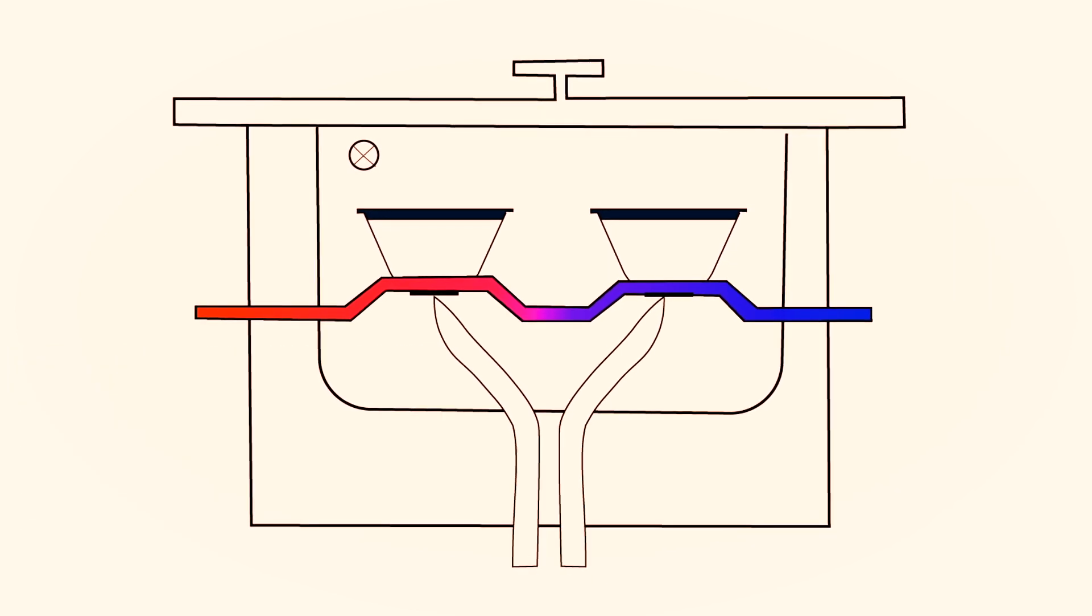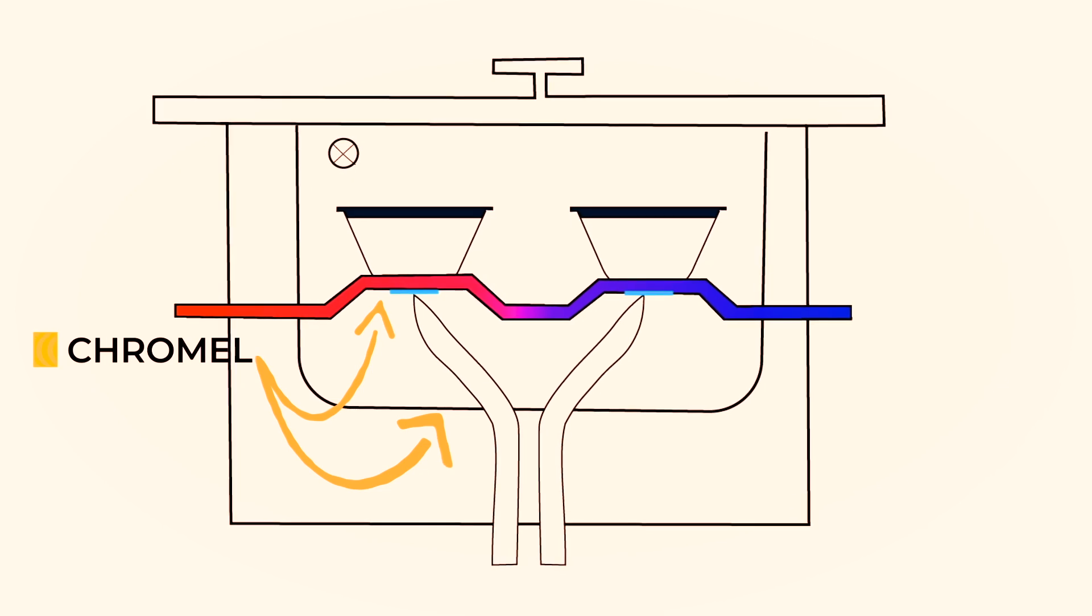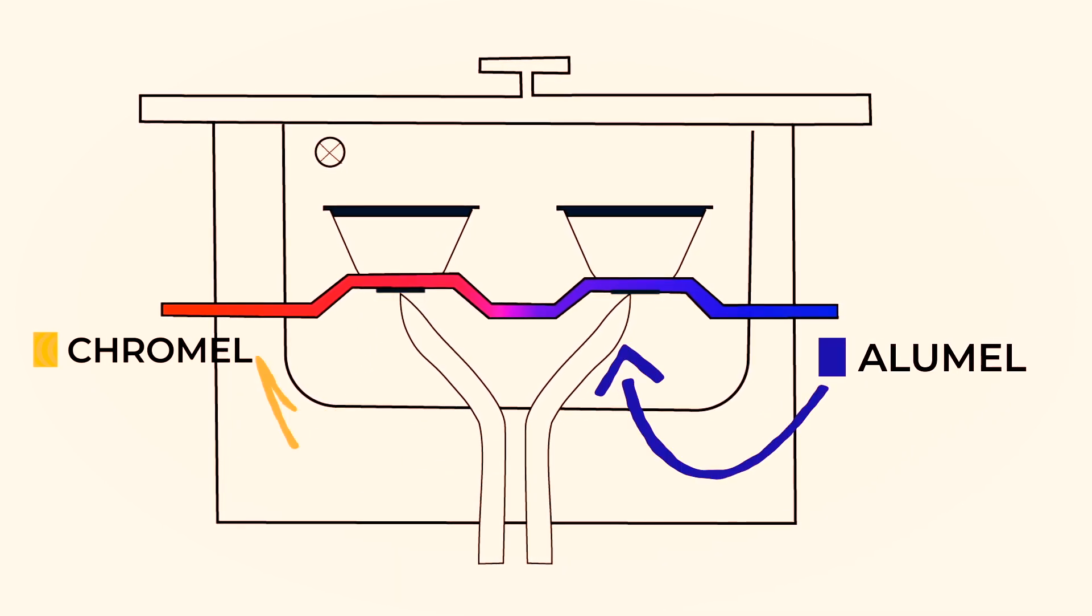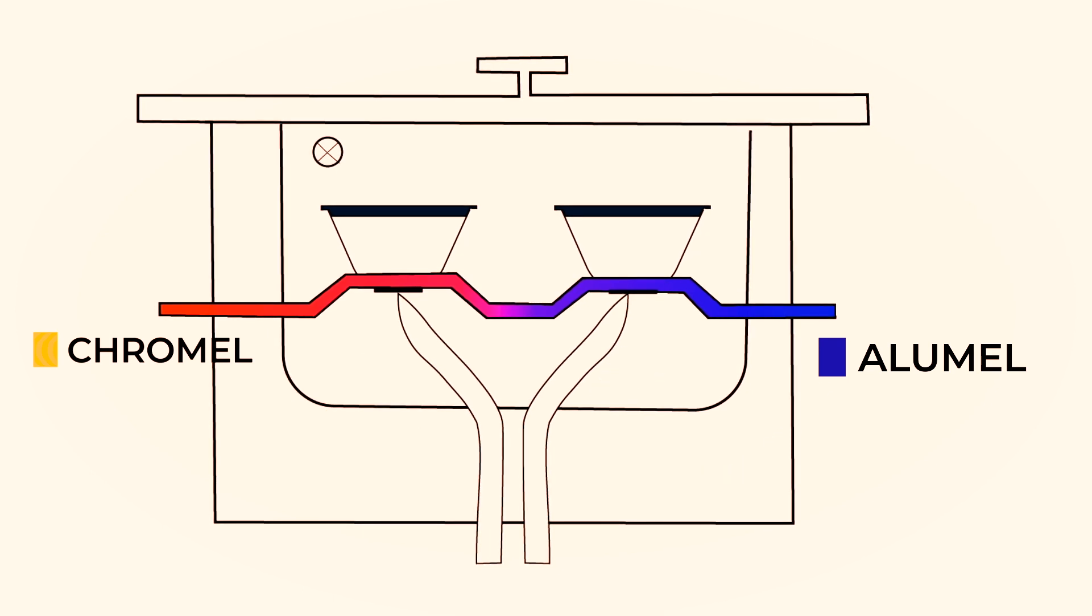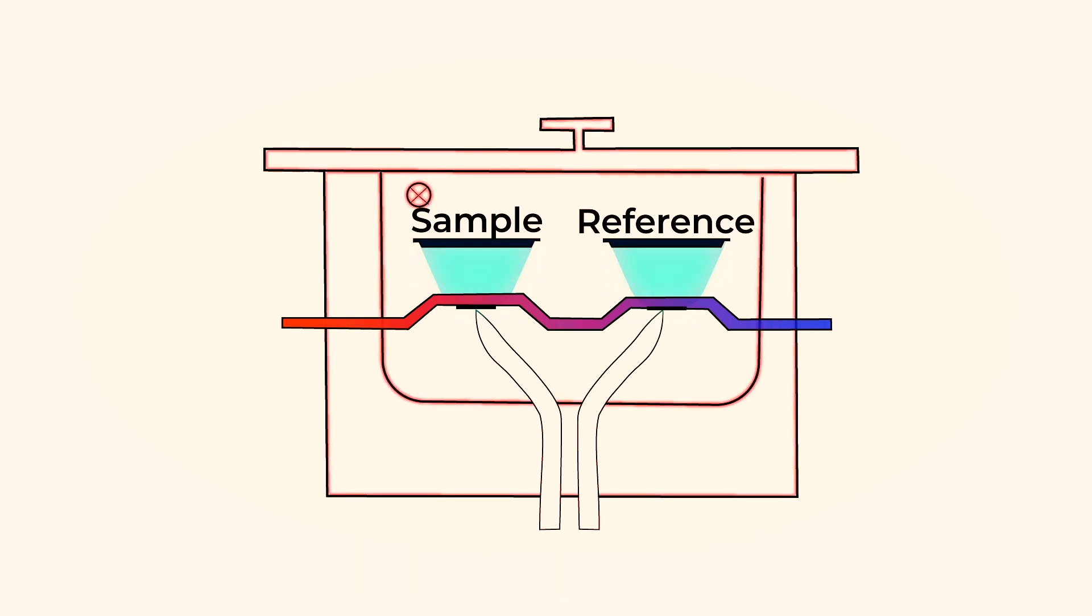The temperature sensors are disk shaped chromel-constantan area thermocouples and chromel-alumel thermocouples that are placed just below the disk. At the start the sample and pans are in equilibrium. As the block is heated the sample and reference also start to get heated. Both these will lag behind the block temperature to a different extent since the heat capacity of the sample is more due to a higher mass.